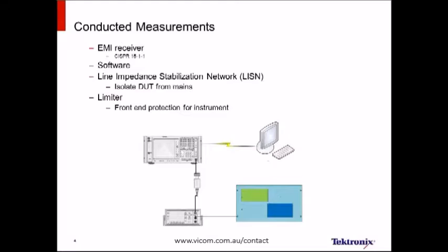The software does two things for us. It actually controls the test itself, but it also generates the test report, and the test report will be specific to the EMI specification that you're working to.